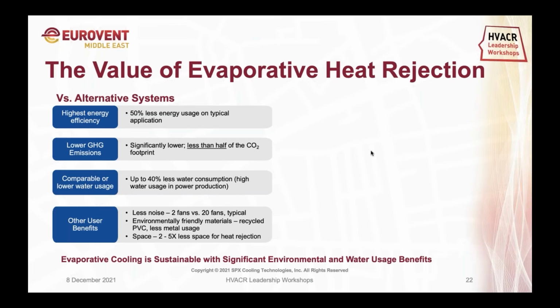Some of the other benefits are noise, which I just covered - 2 or 3 fans in the cooling towers versus a large number of fans on air-cooled chillers. The environment too: cooling towers are made mainly of PVC fills with very little metal, which is good for the environment. And finally, space - I gave the example of the roof of the building, where instead of 8 air-cooled chillers we end up having only 3 cooling towers, 3 fans versus around 20 to 25 fans. In terms of space, the dimensions of those cooling towers were almost 5 times less than the footprint occupied by the 8 air-cooled chillers.